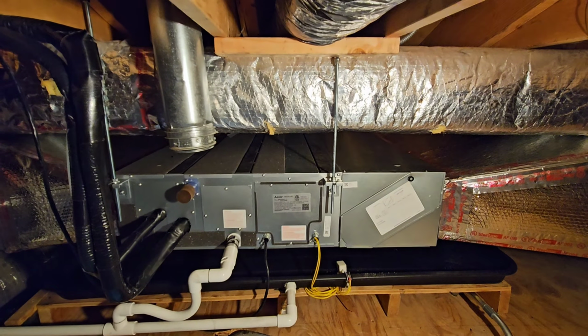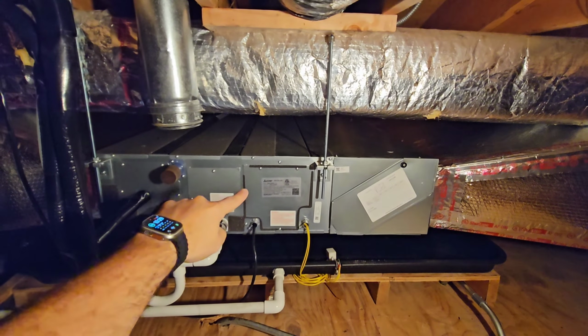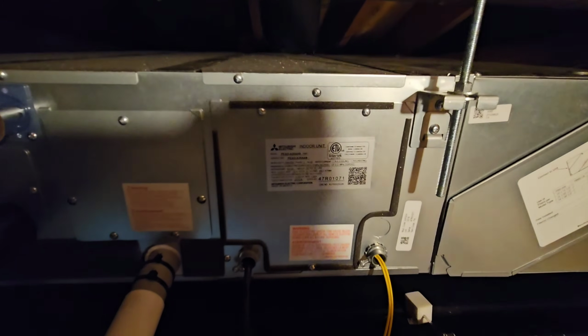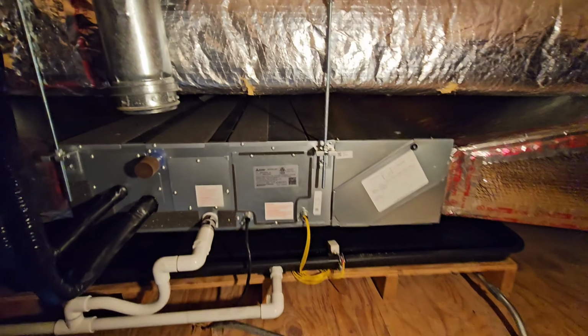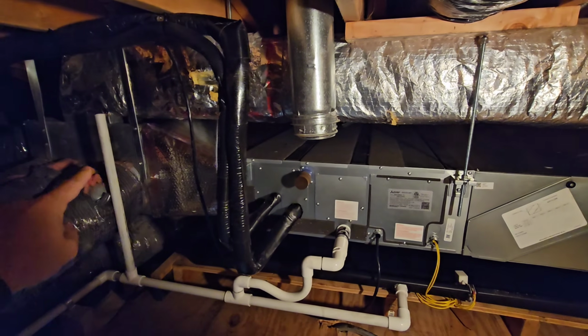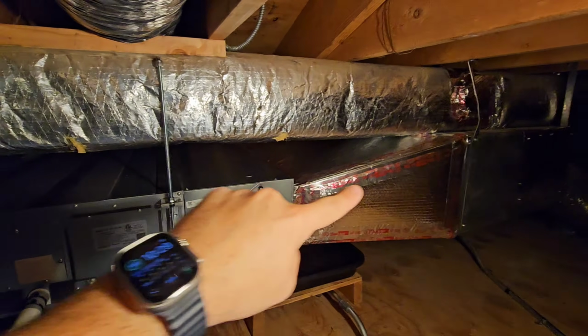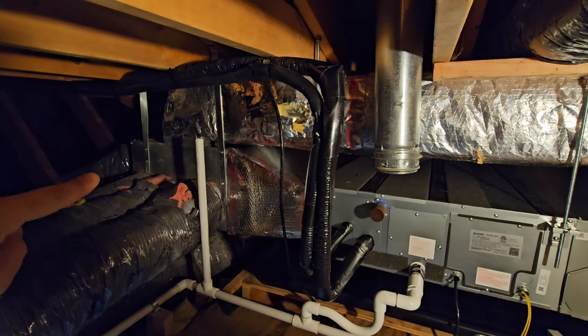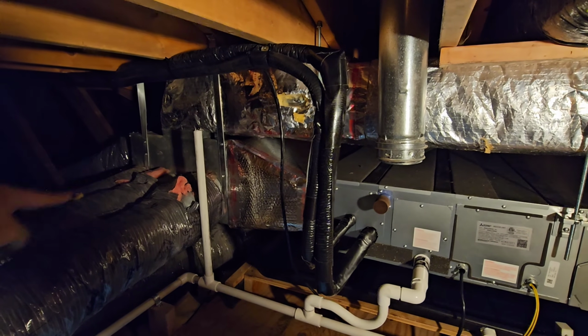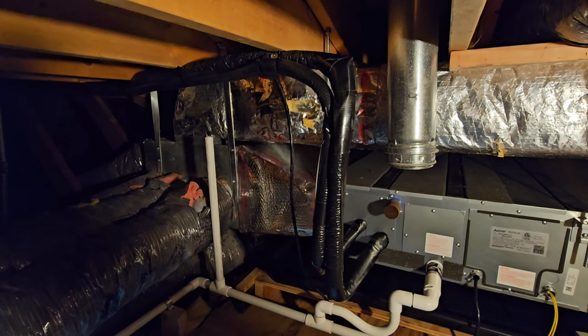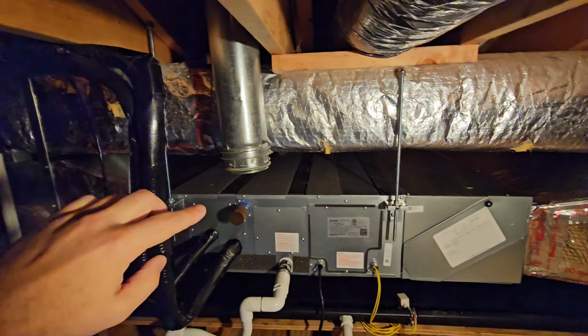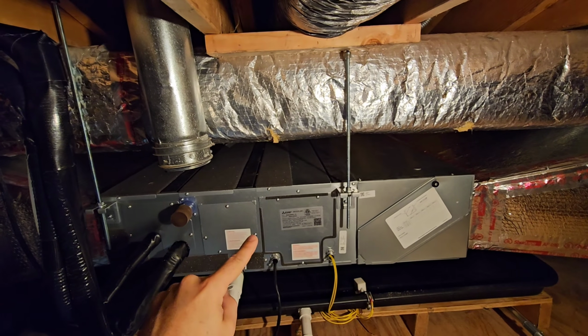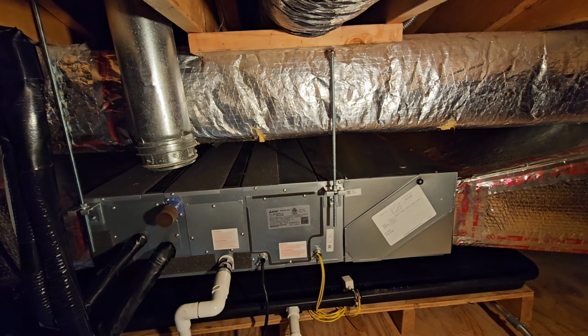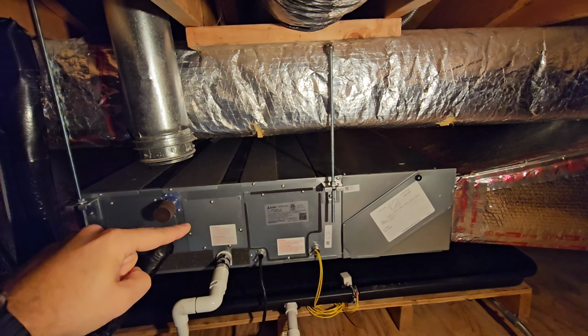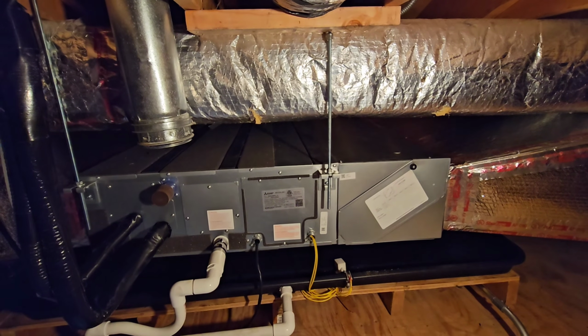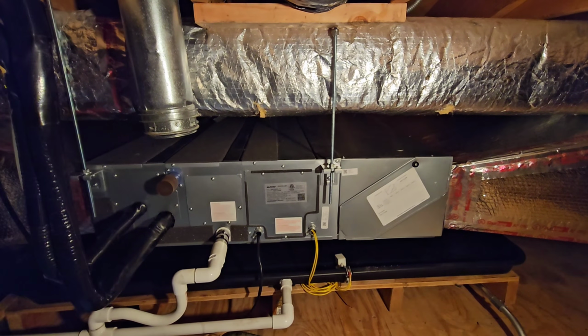So what we did is we replaced it with a compact horizontal air handler from Mitsubishi Electric. We have a PE80. It's a 30,000 BTU unit. And we also modified the ductwork, not only to make the unit fit, but one of the issues was our plenum box and the way it fed all the supplies wasn't getting proper airflow. So we made some adjustments in there. This air handler is connected to the same outdoor unit we took a look at outside, which is powering not only this air handler, but the coil downstairs for the furnace. And this unit is going to be doing all the heating and cooling of the upstairs.